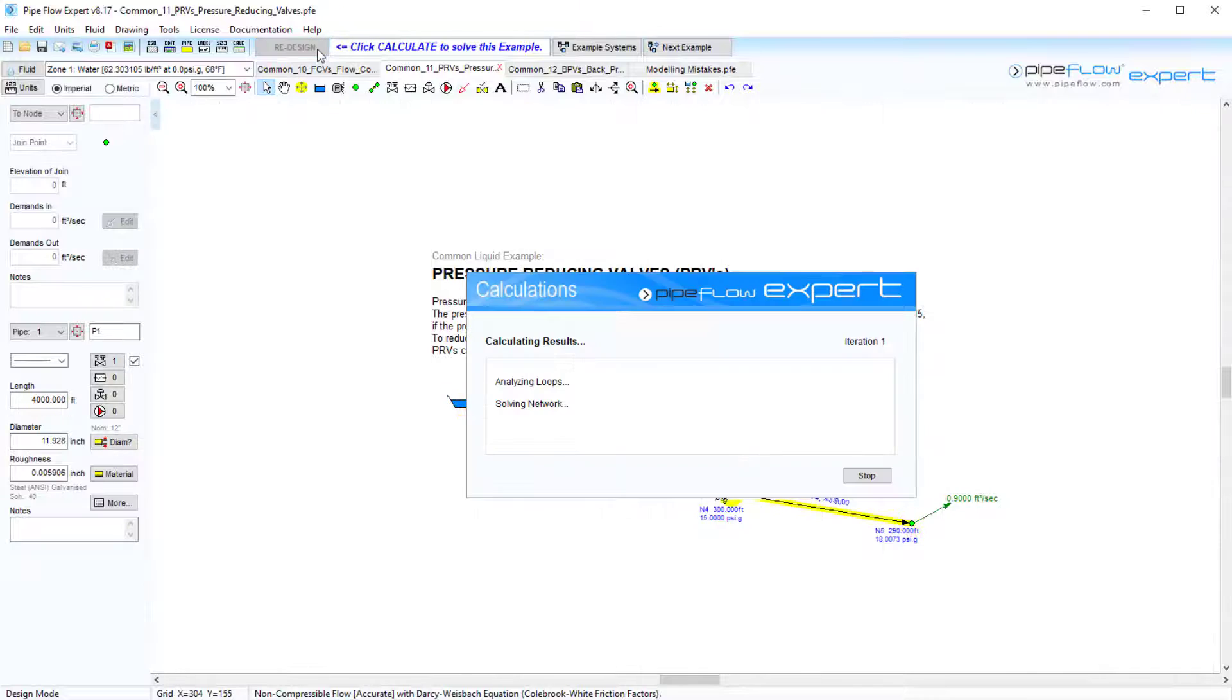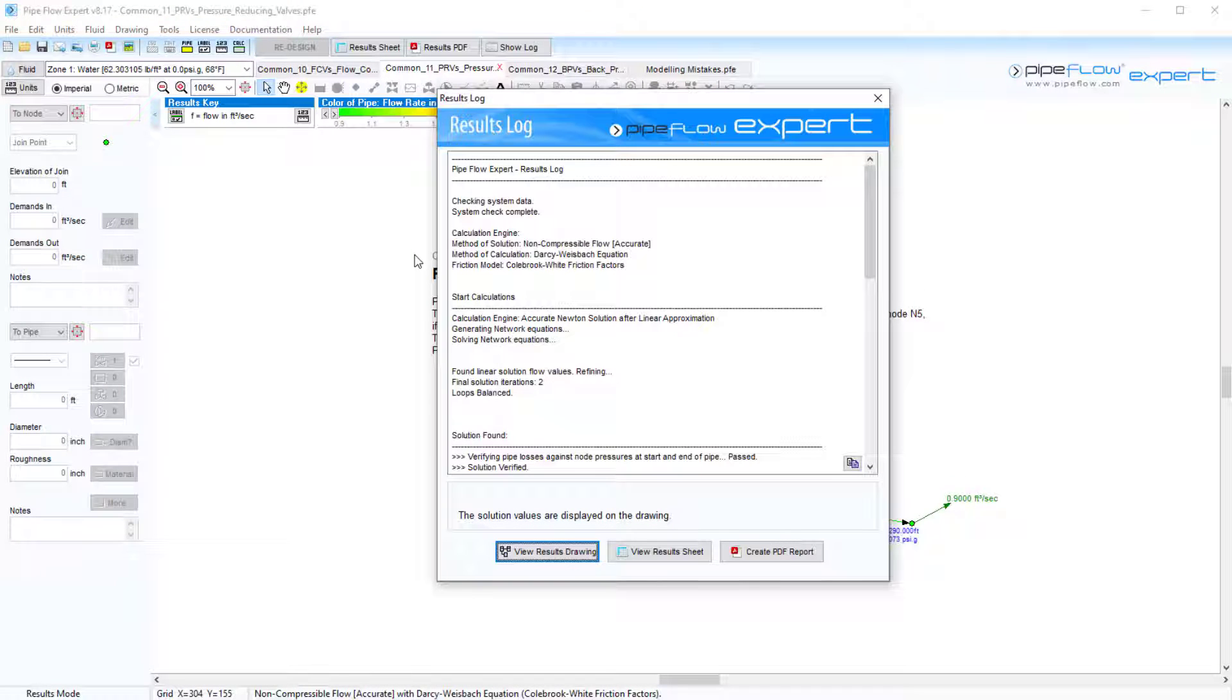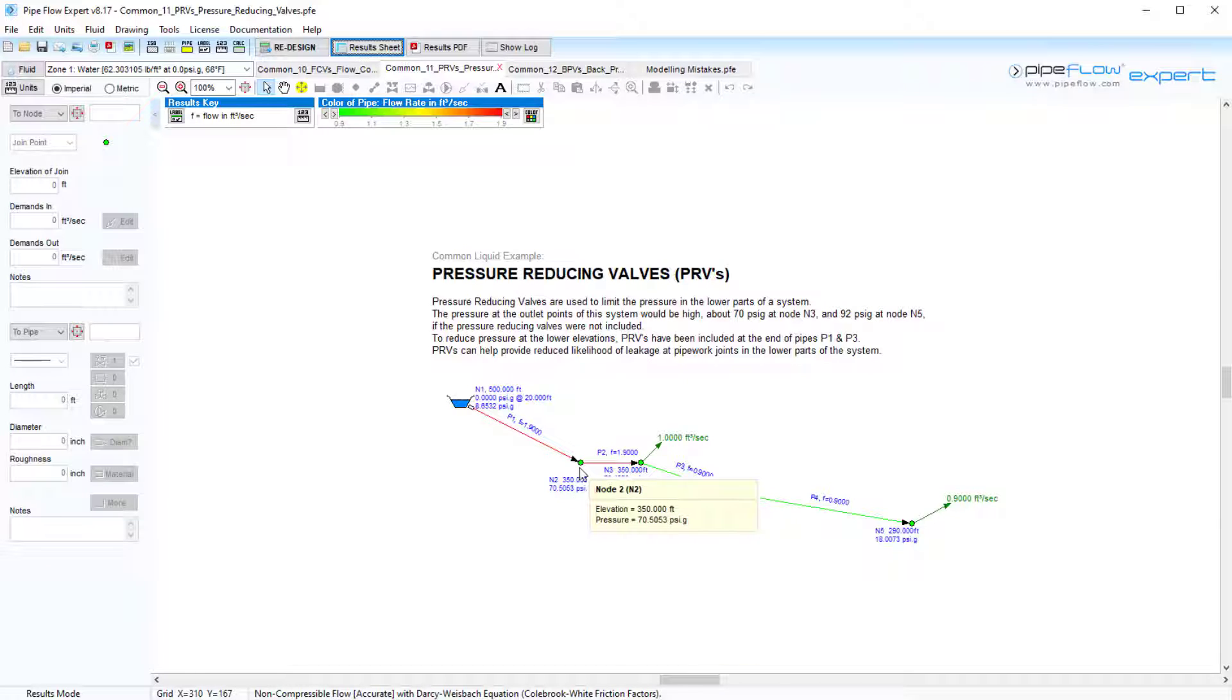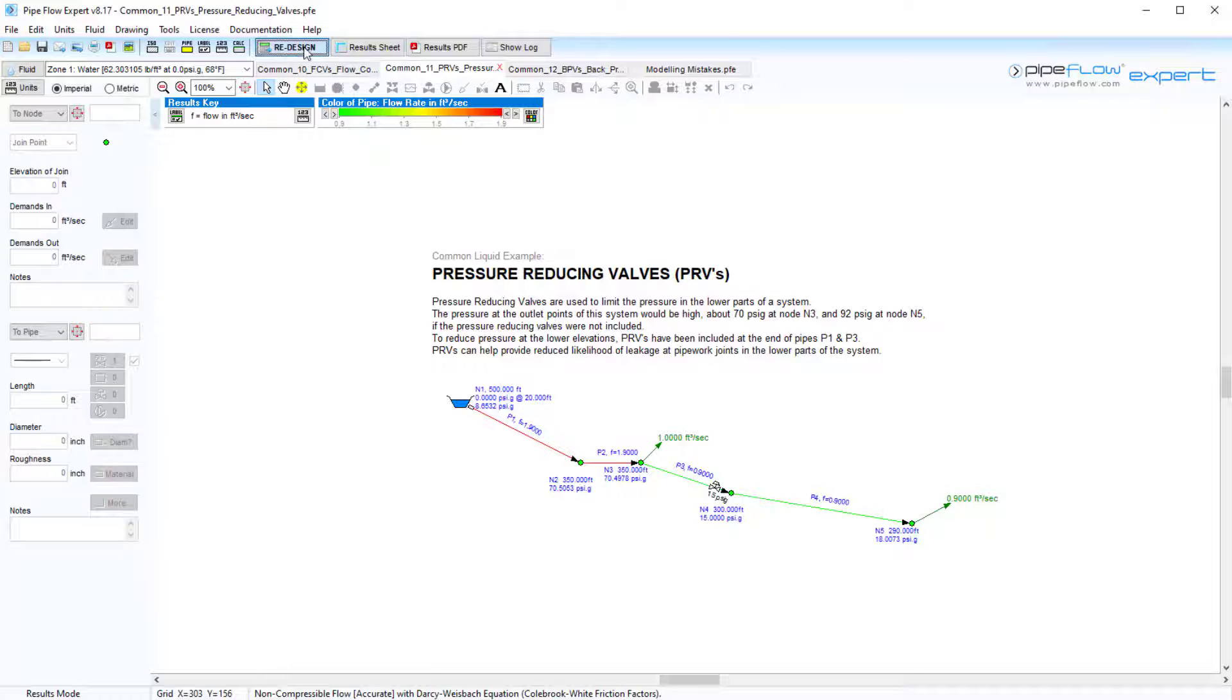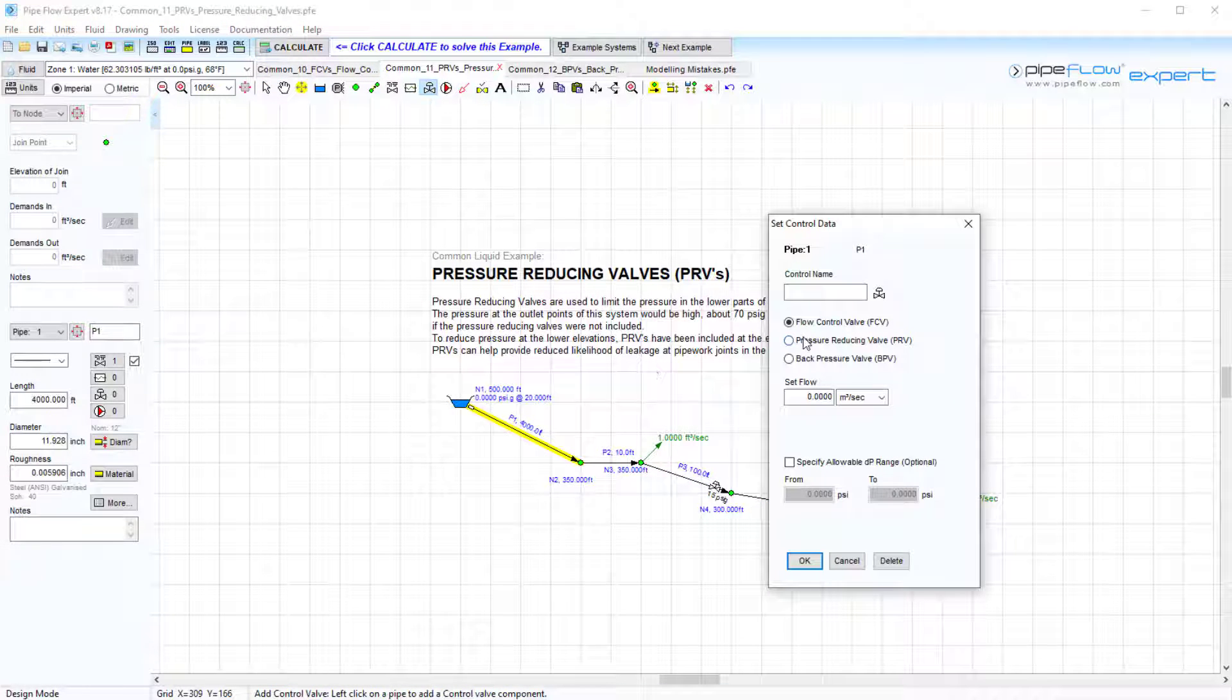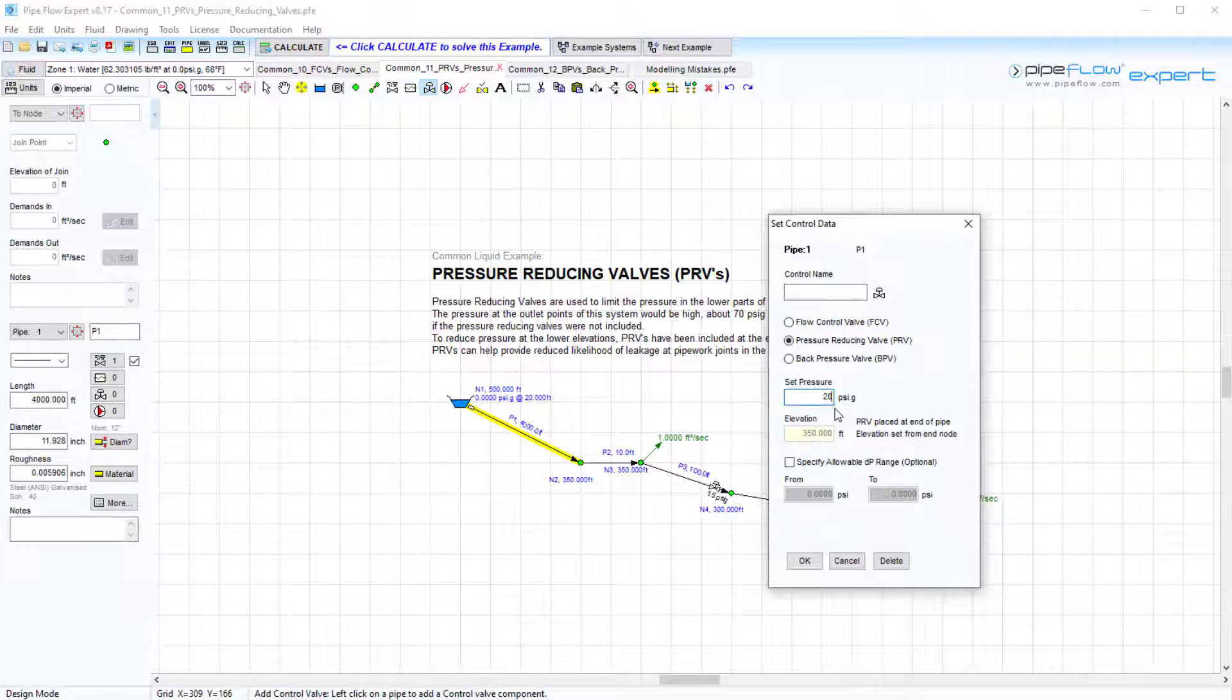The pressure at node 2 is calculated to be as high as 70 psi gauge, so let's introduce the PRV to limit the pressure to 20 psi. The elevation is set to the elevation at the following node since the software assumes the valve is placed at the end of the pipe.